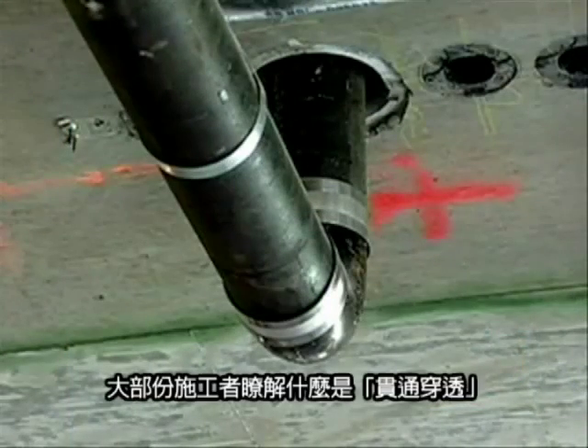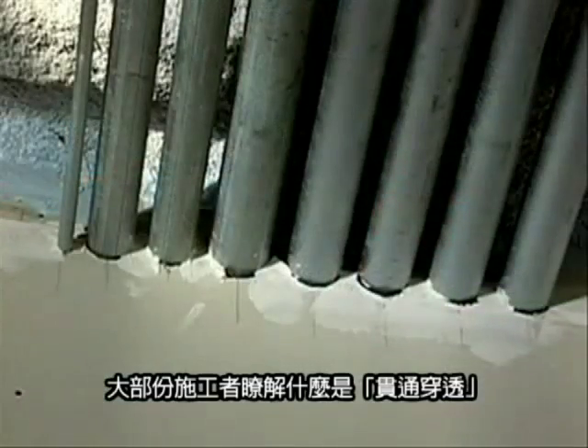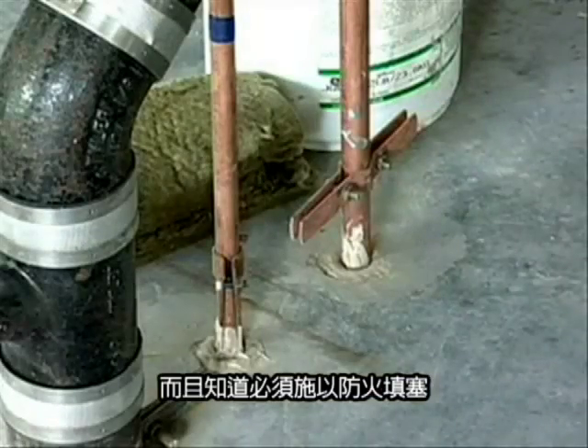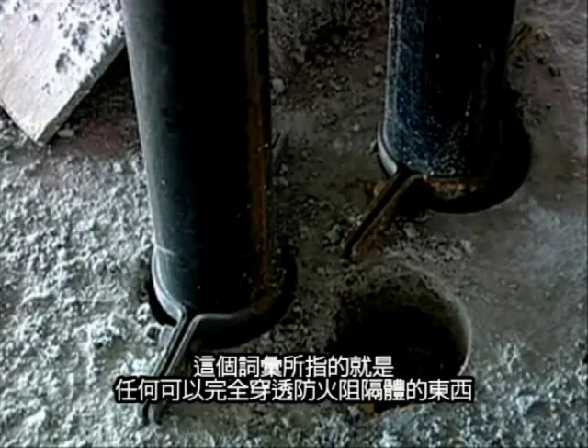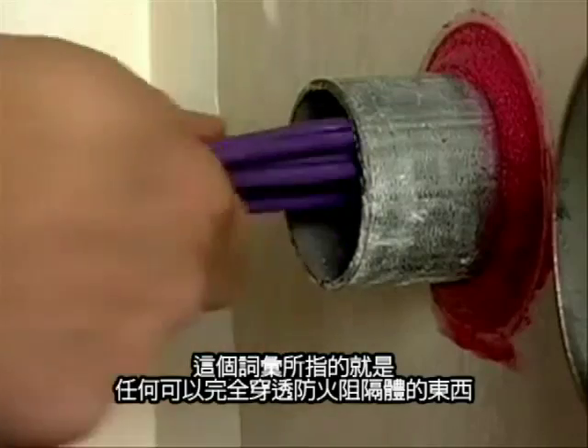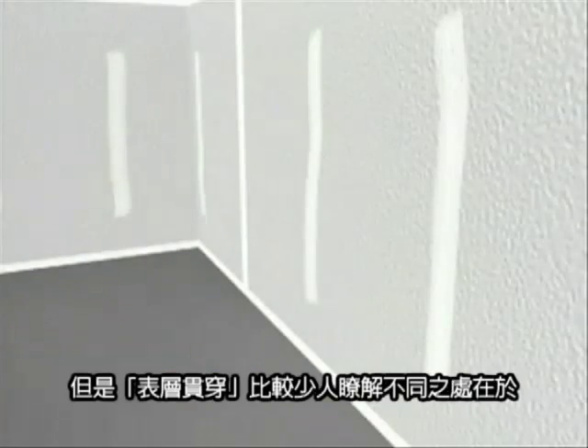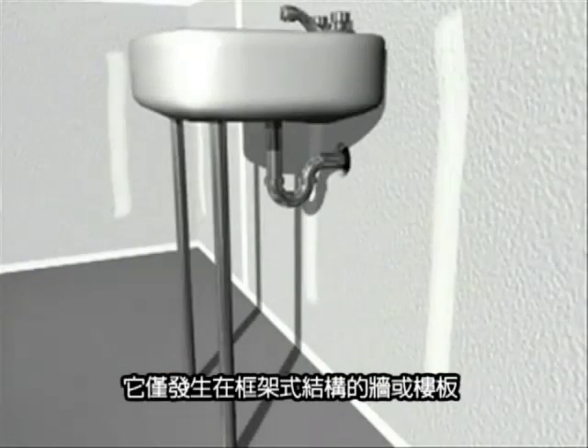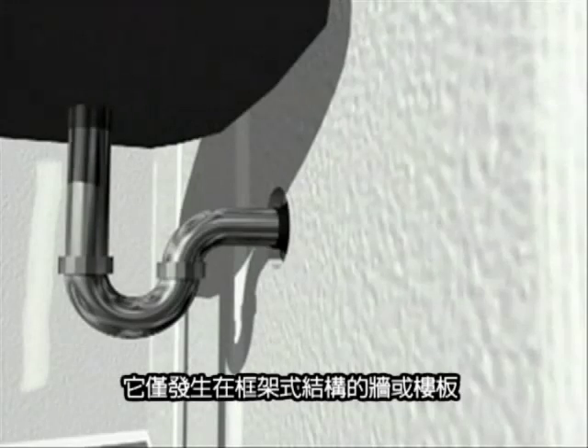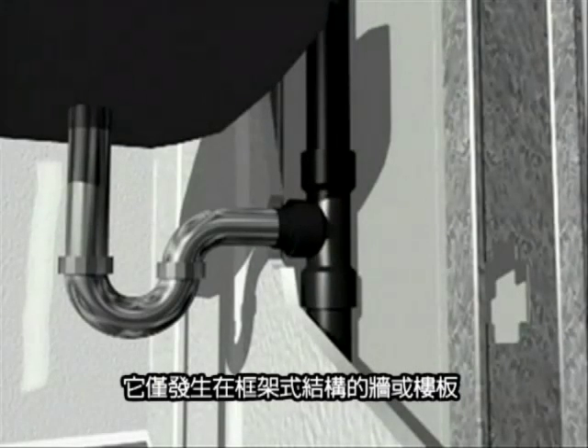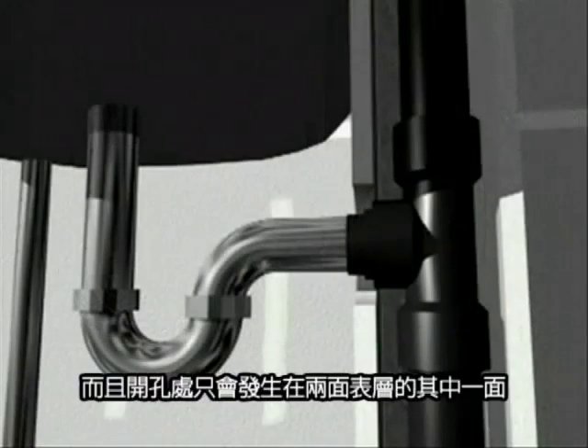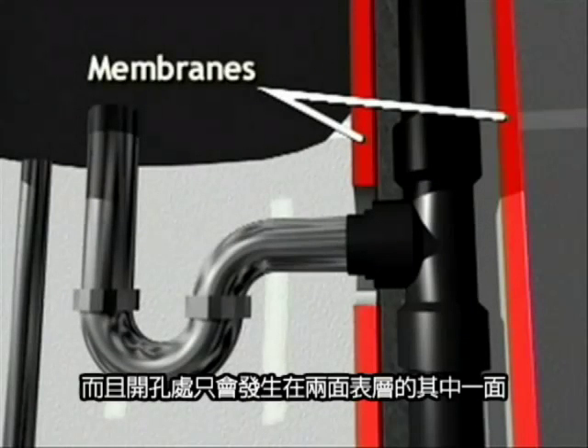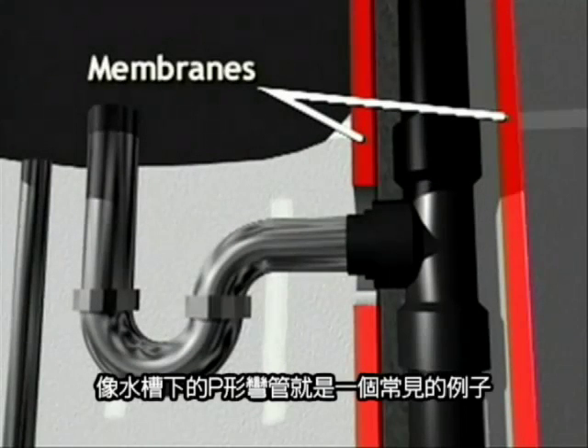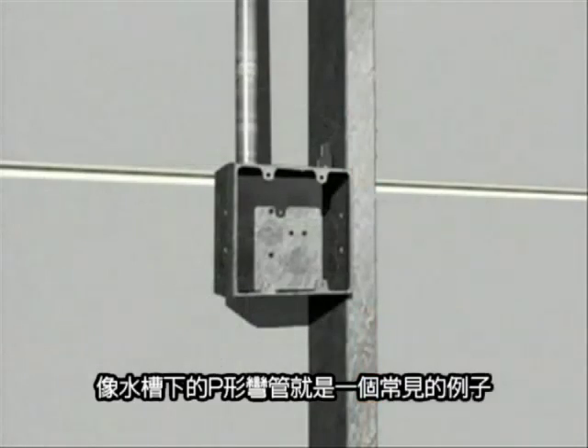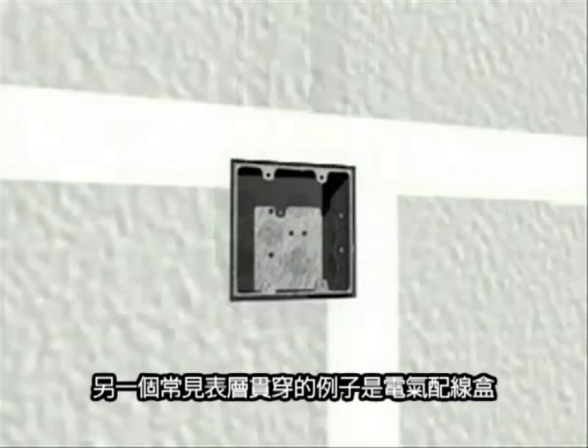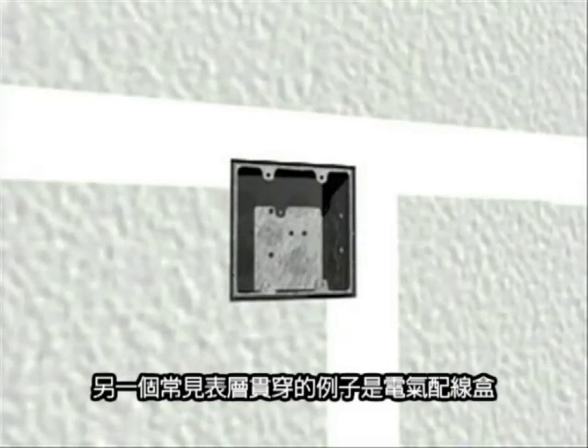Most tradespeople already know what a through penetration is and that it must be sealed. The term simply refers to anything that passes completely through a fire barrier. A membrane penetration, however, which is far less widely understood, differs in that it occurs only in framed walls or floors and breaches only one of the two membranes. A common example of this is a P-trap. Another common example of membrane penetrations are electrical boxes.